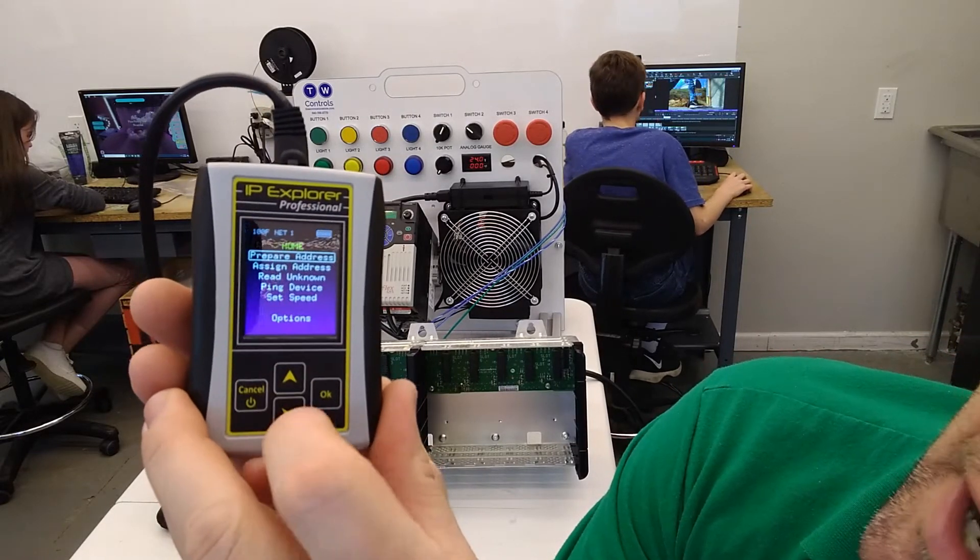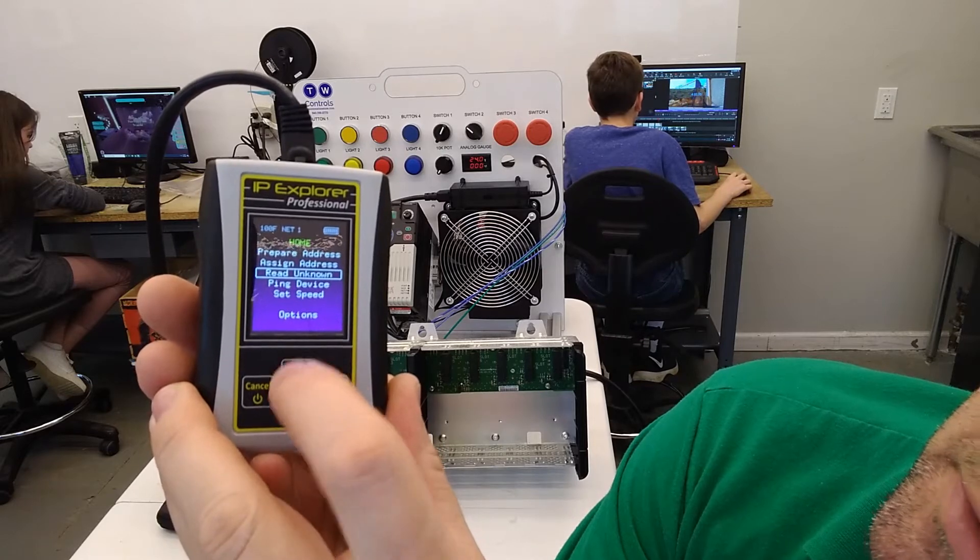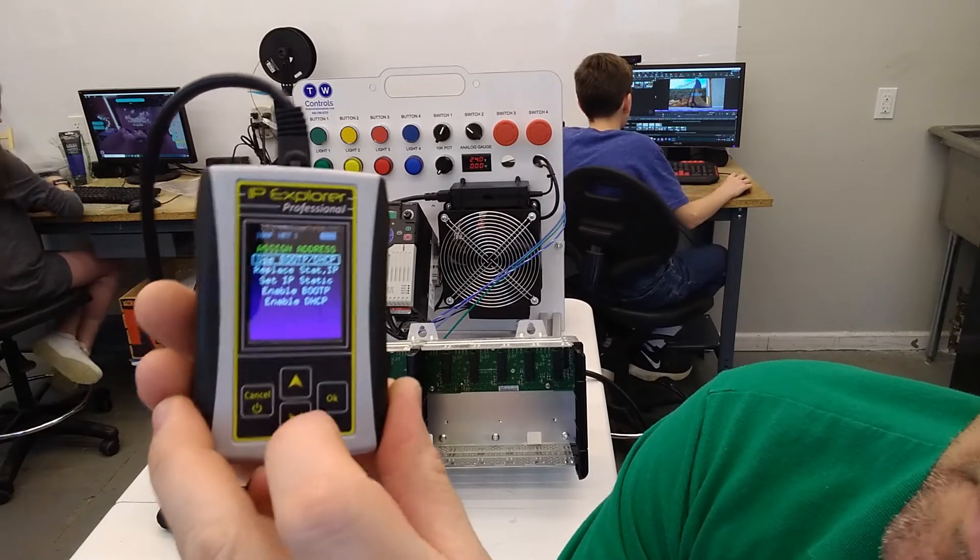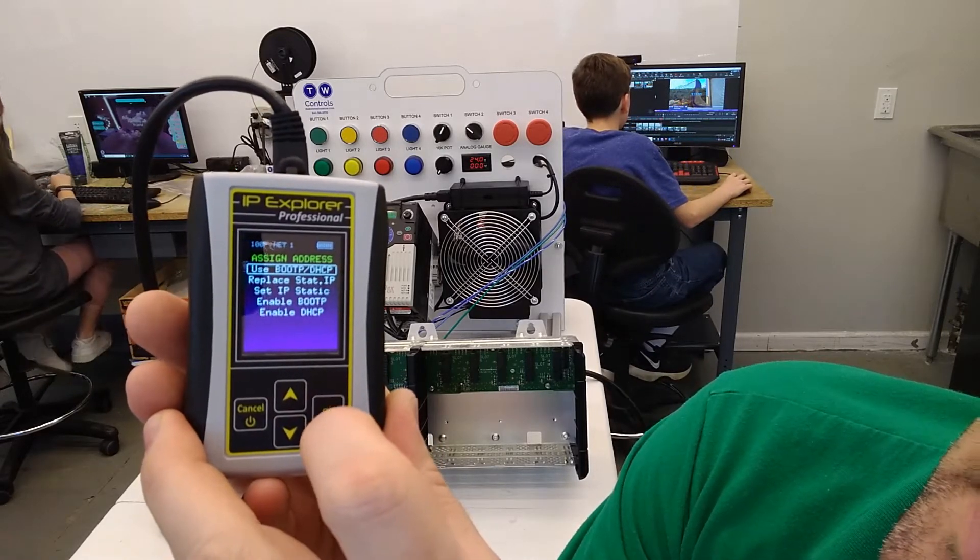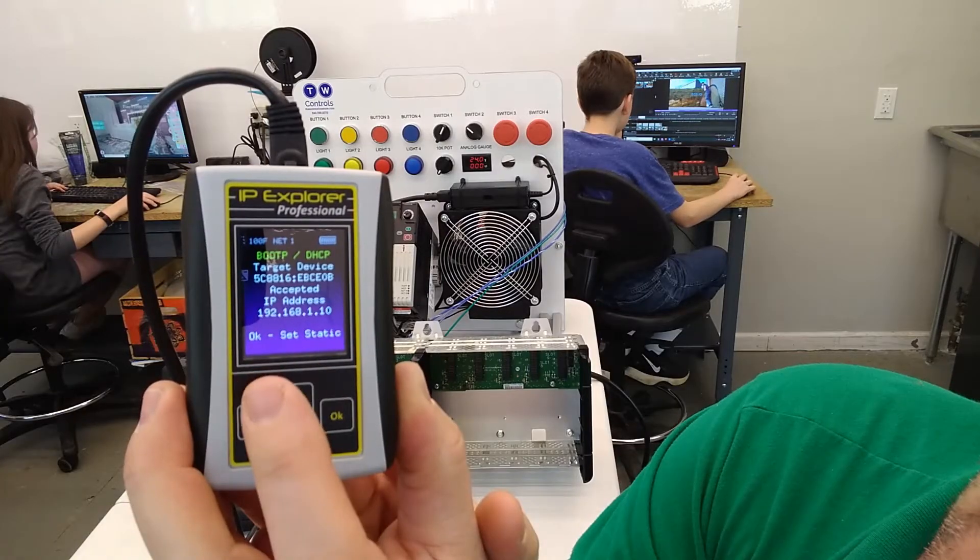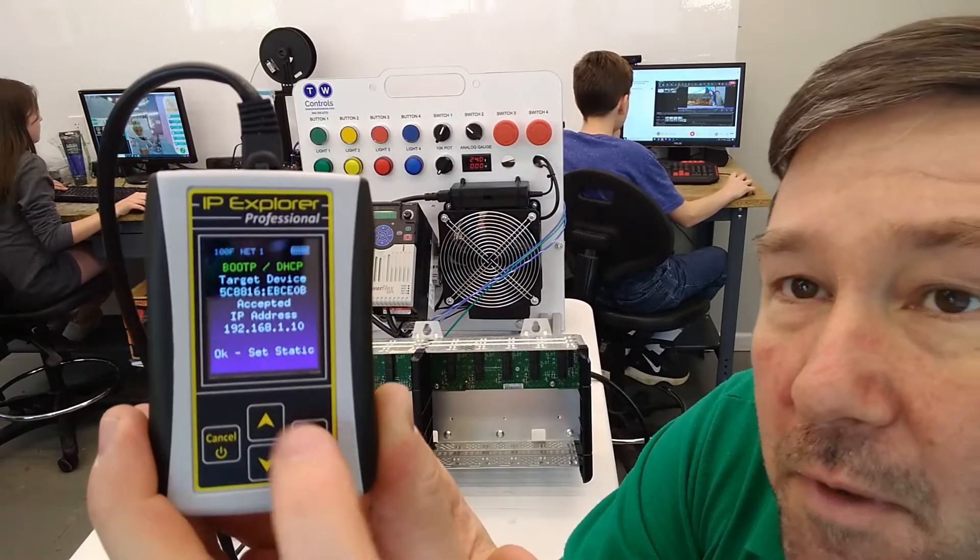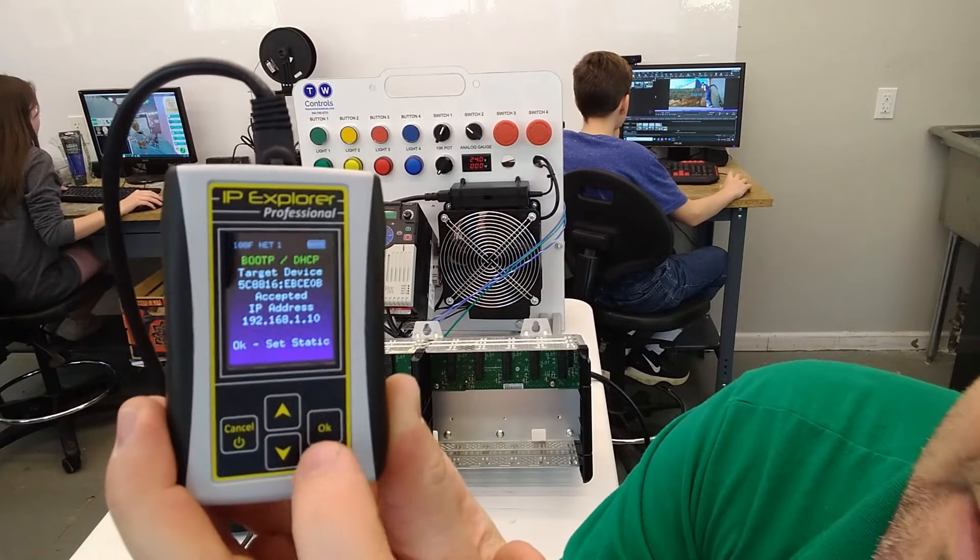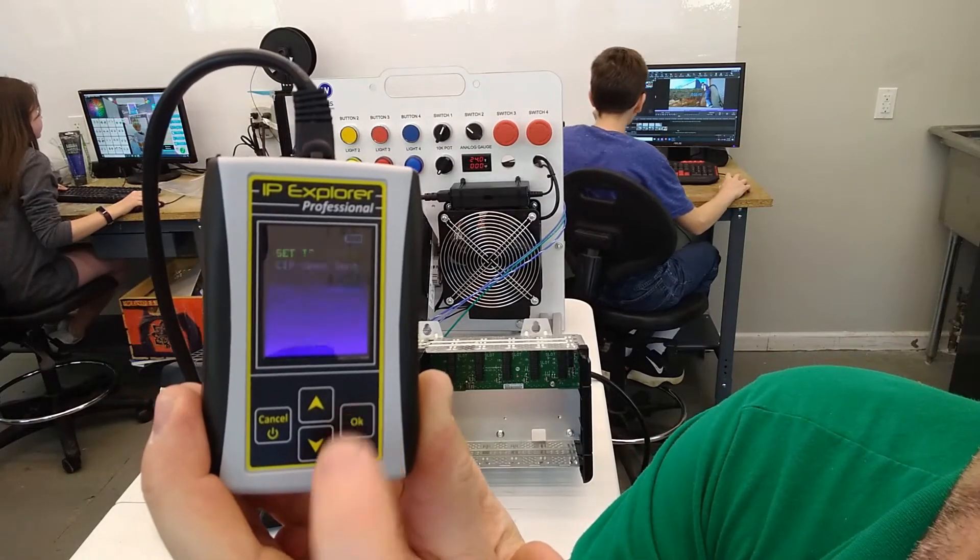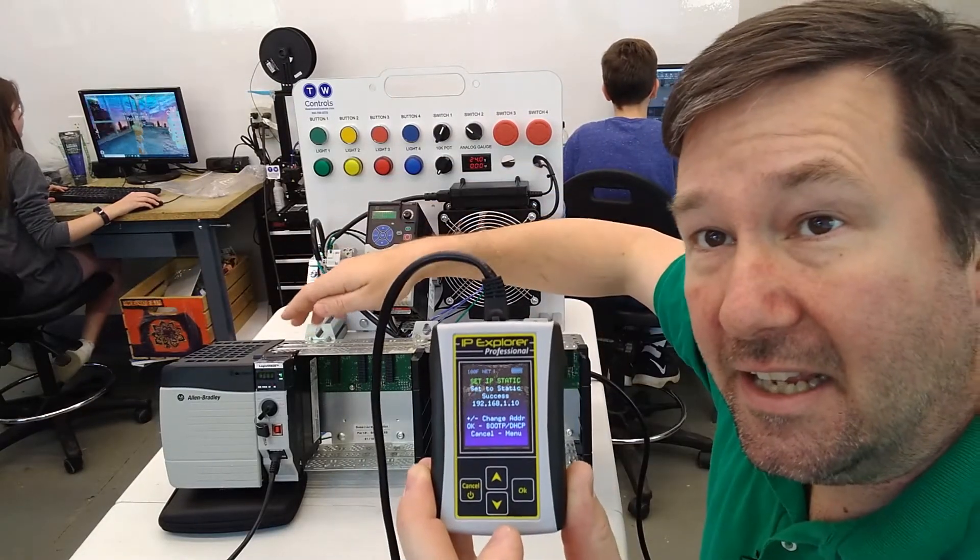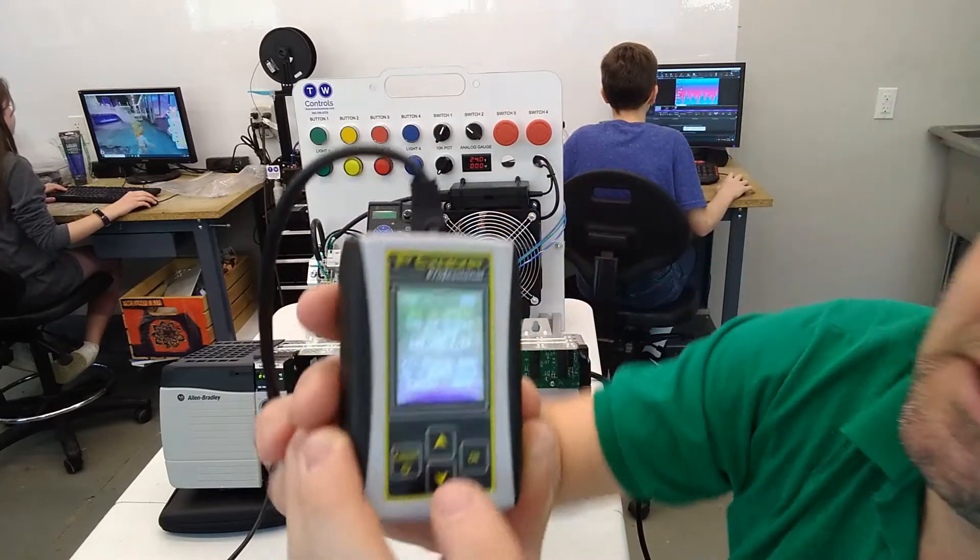I'll go out, and now we are going to assign address, and we're going to do it via bootp.dhcp. And it says target address accepted. And from the bottom of this screen, we can go ahead and set it to static. So I'm going to click OK. Now that address is static in our ControlLogix processor.